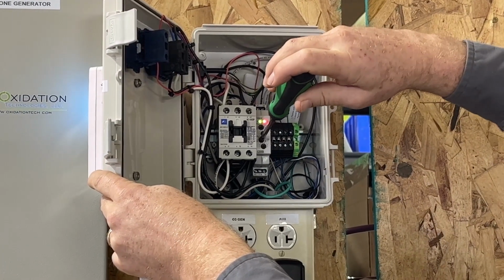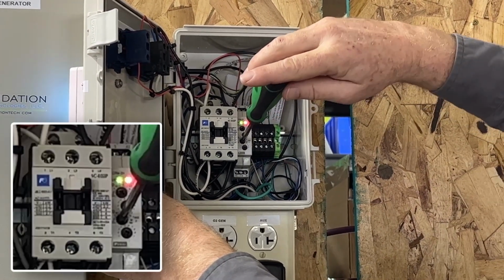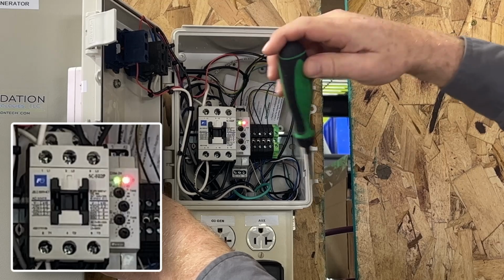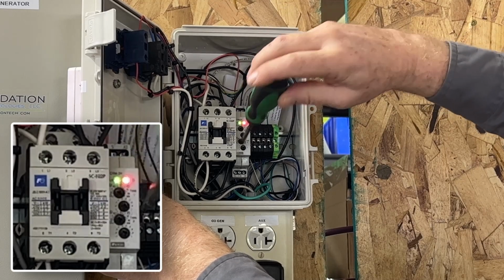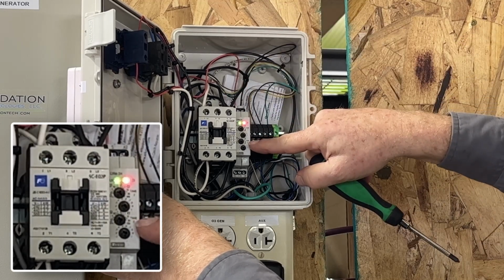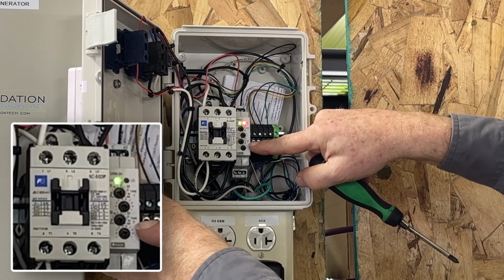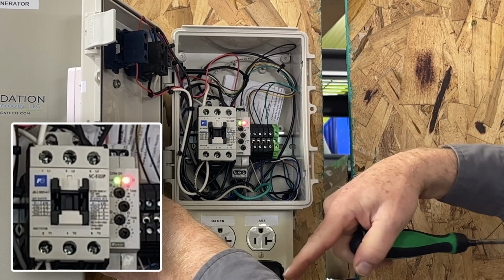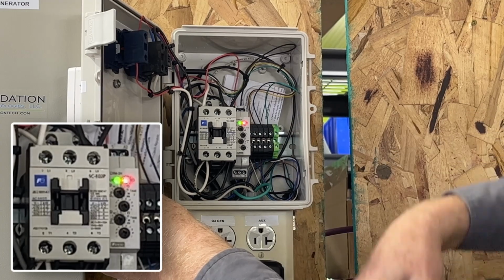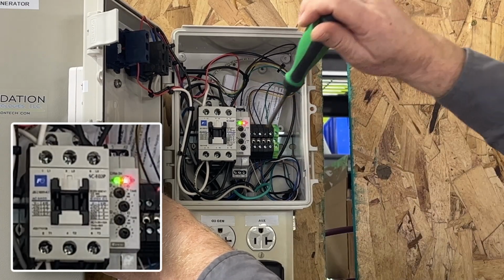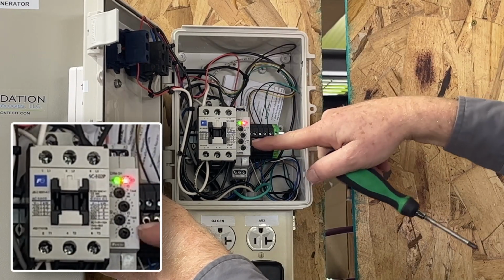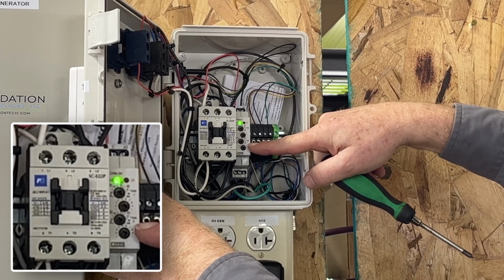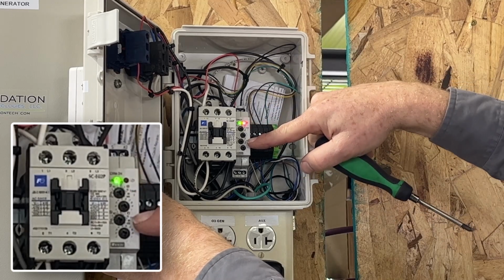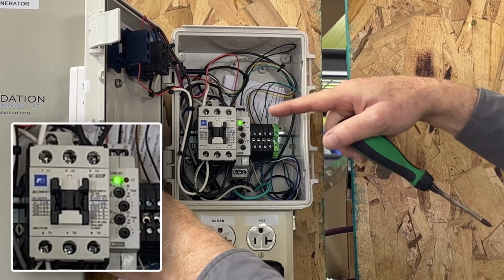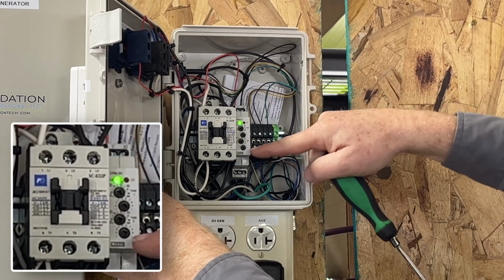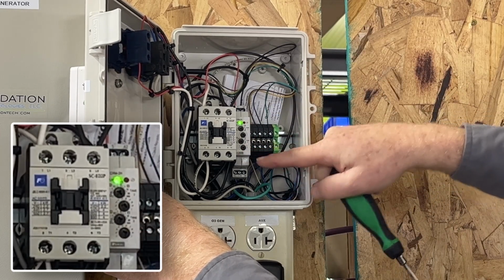The bottom one adjusts how long between those on cycles, and typically you're going to want to have it for maybe 3 hours or so, so that every 3 hours your pump will turn on for a couple minutes to put some ozone in this tank. But it could be as long as 10 hours or 100 hours. A recommendation is 3 to 5 hours, then it'll turn on. And again, this adjusts the resolution.